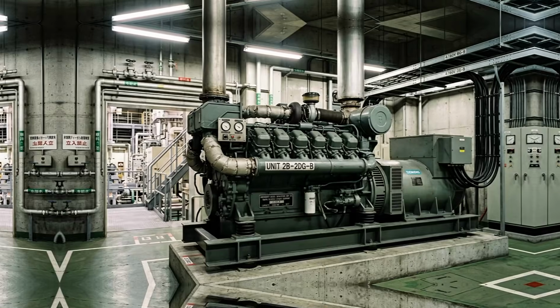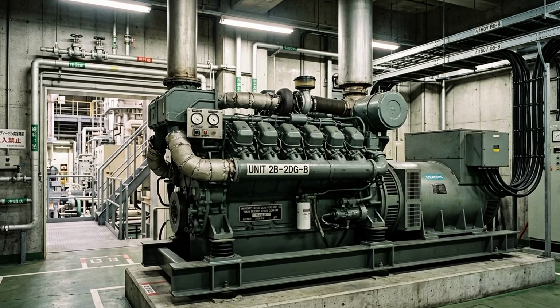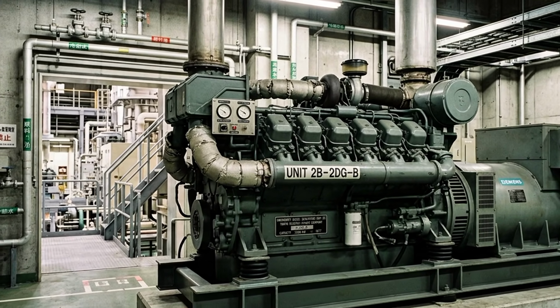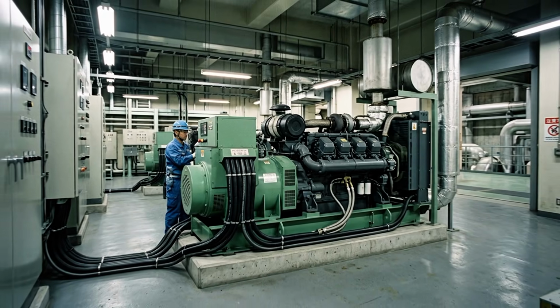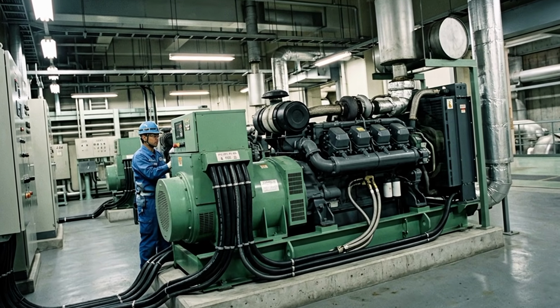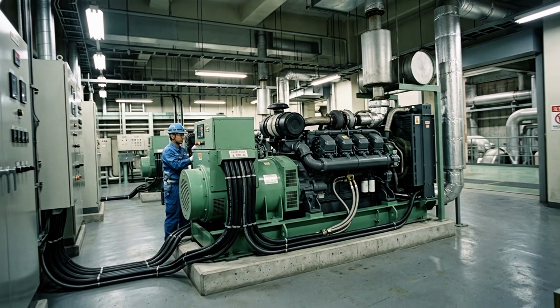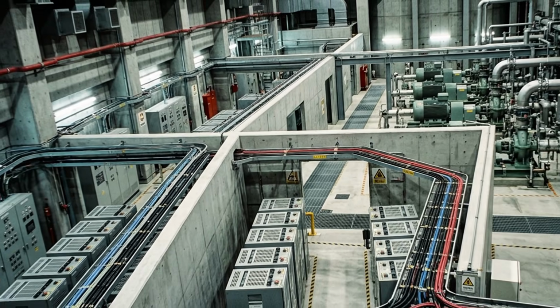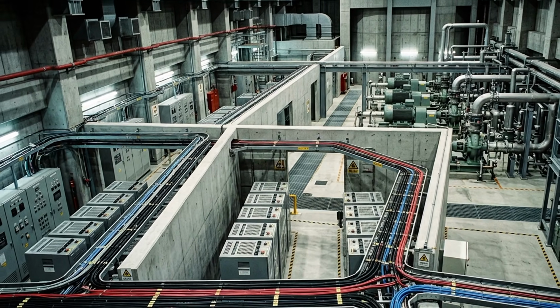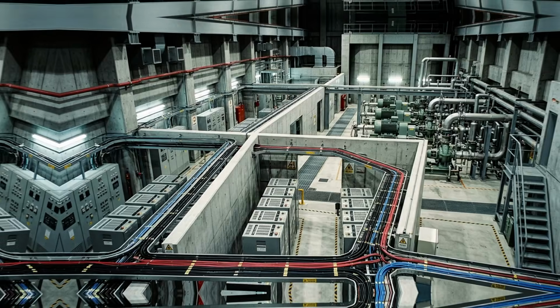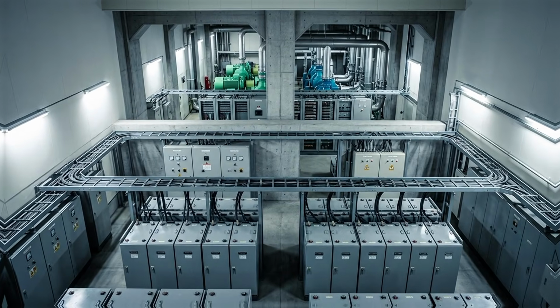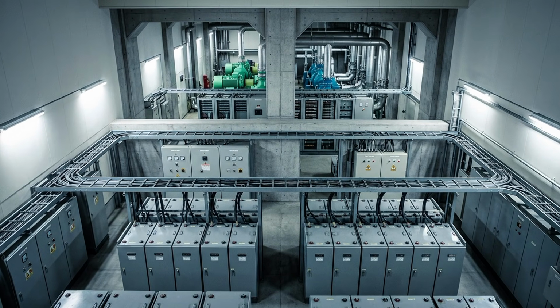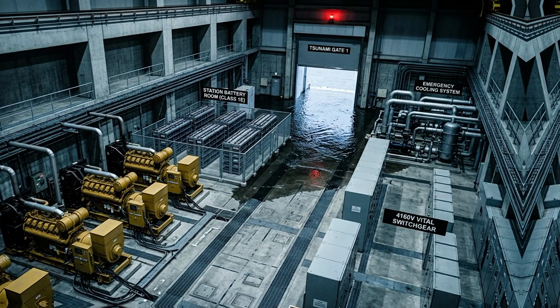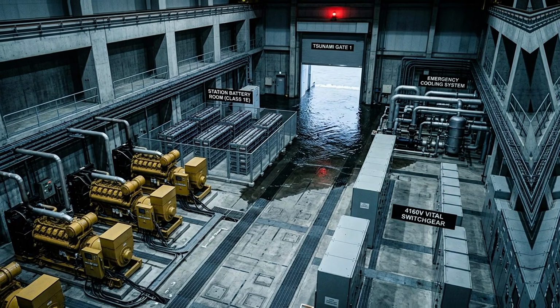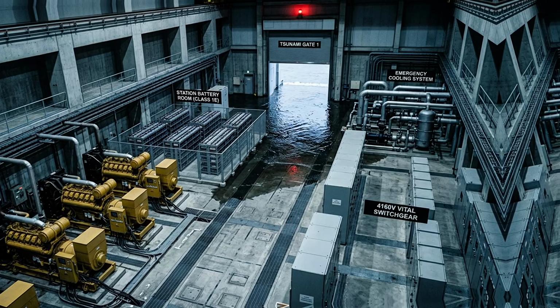Fukushima Daiichi was built around a principle known as defense in depth. Safety did not depend on one machine. If normal electrical power was lost, emergency diesel generators could provide AC power. If AC power became unavailable, batteries could provide DC power for essential controls and instrumentation. Different cooling systems provided additional protection. The architecture was built around layers, but layers only work when they are independent enough to survive the same threat. That would become the central weakness at Fukushima.